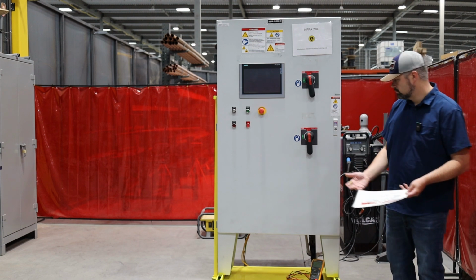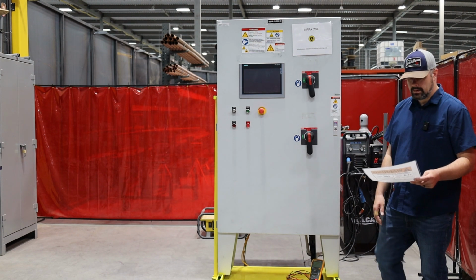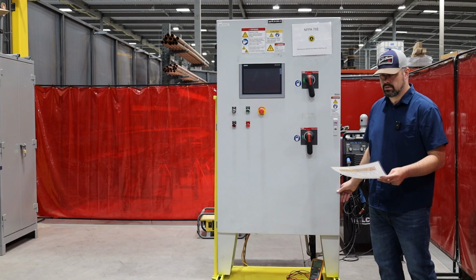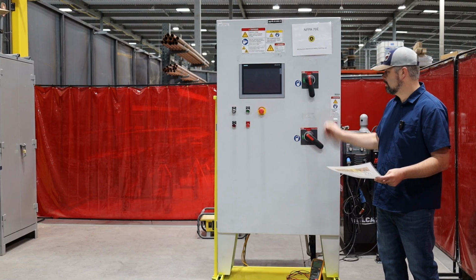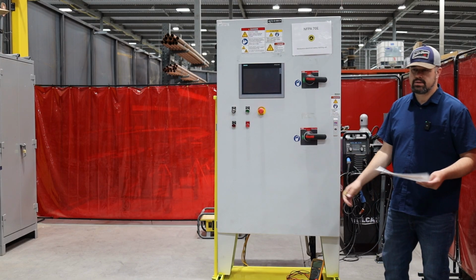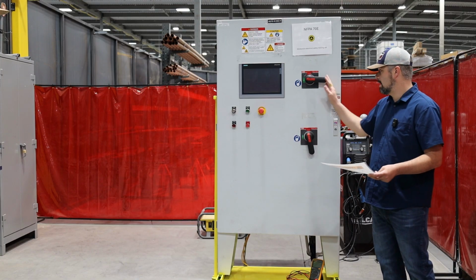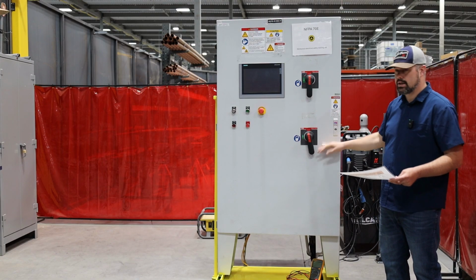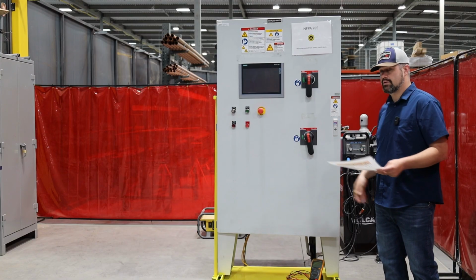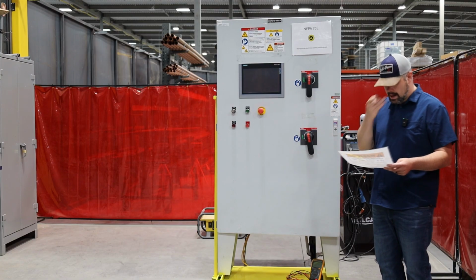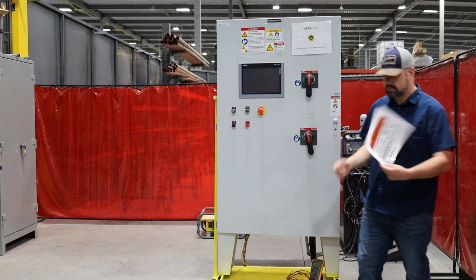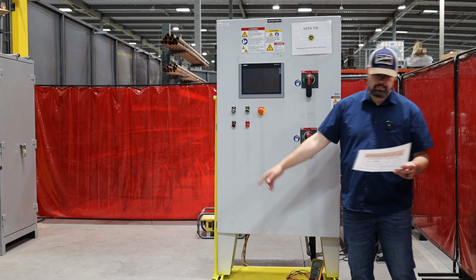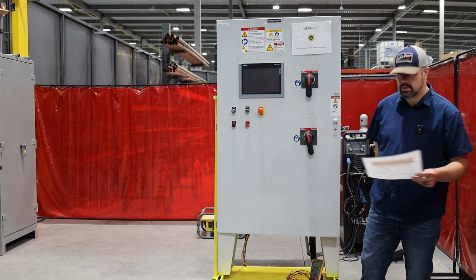Job is coming up to this cabinet. We know that before we open this door, we are either going to kill power and do a live verification, or we're going to leave power on and bypass this little thing here and open it to be able to look and see if there's a trip breaker. Before we do any of that, like we talked about with this particular label, we need to set up our barrier at 42 inches.